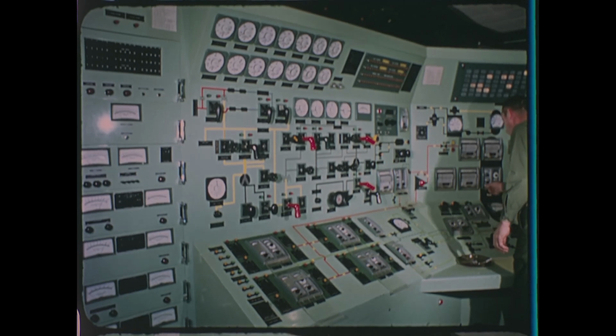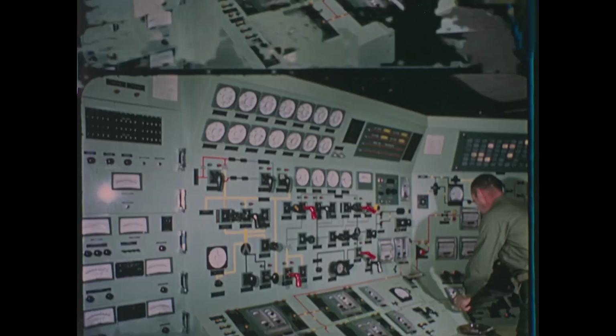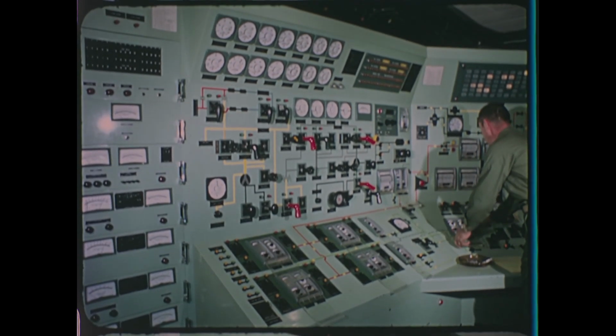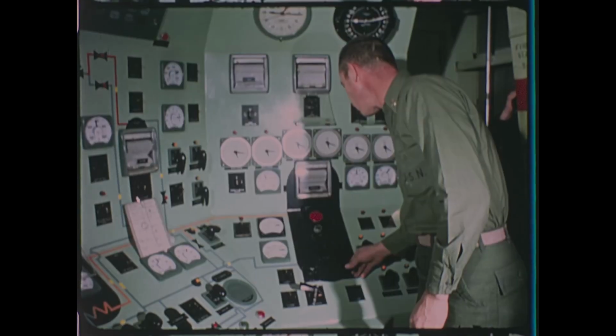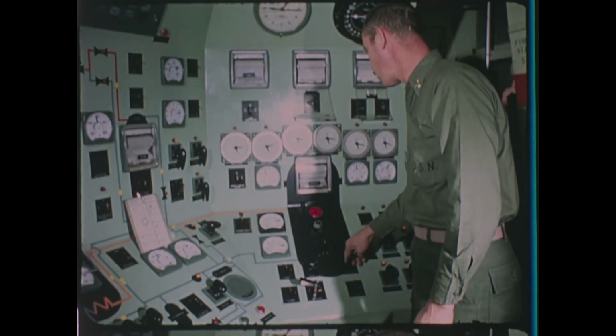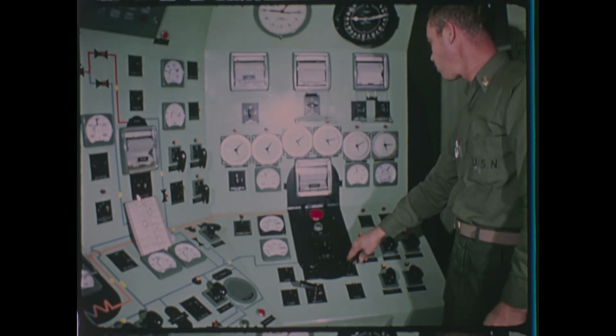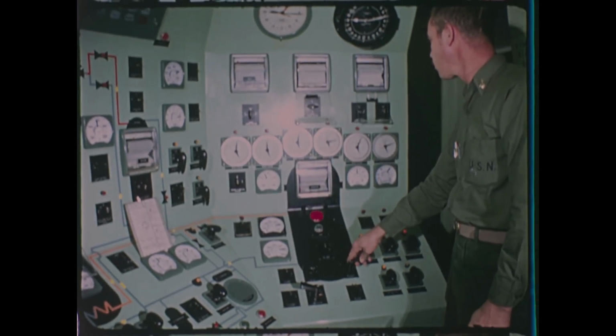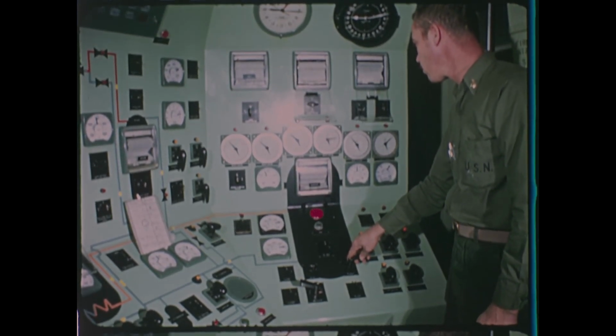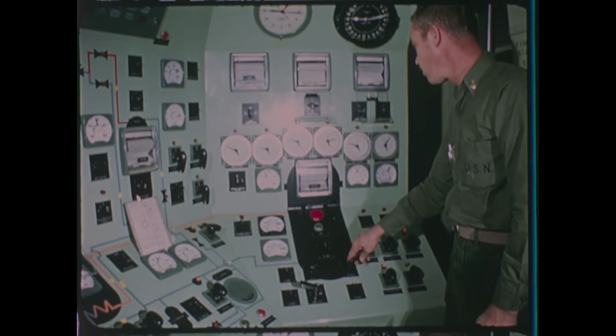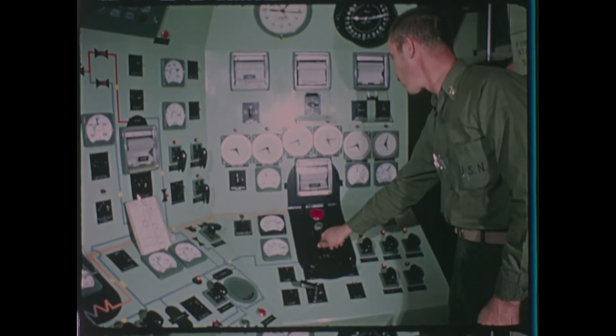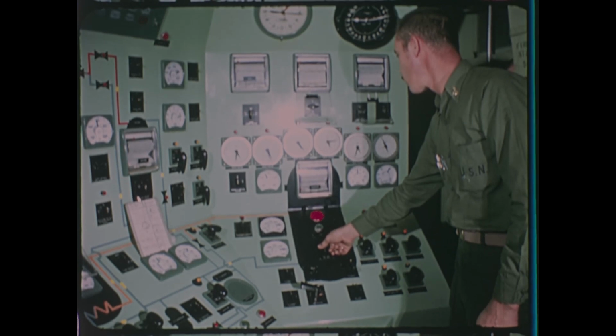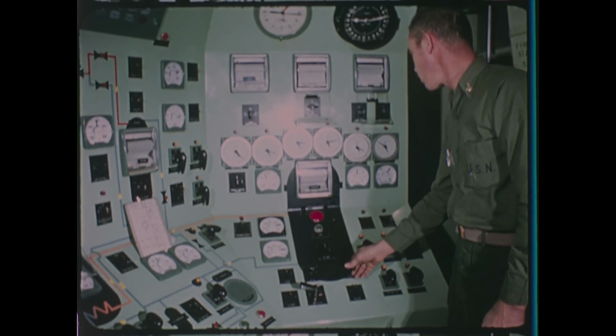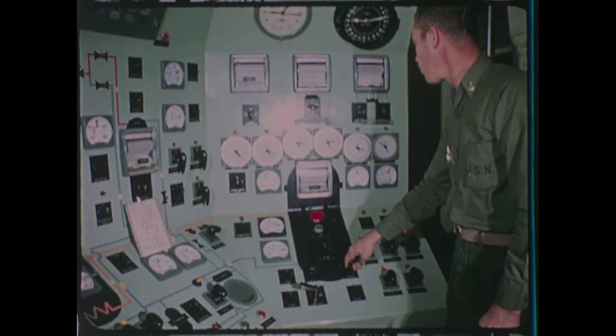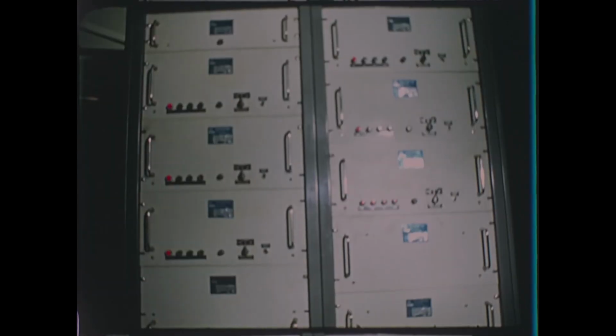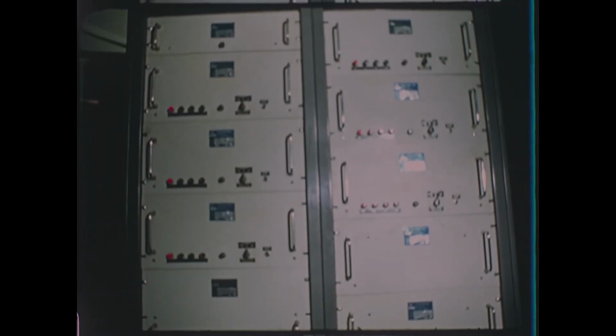To shut down the reactor with rod selector switch in the all position and speed selector in slow, operate rod motion control switch to the in position. Adjust individual rods to maintain rod position within 1/2 inch of each other. Should a low pressure annunciator alarm be received, place the low pressure scram bypass switch in bypass to continue with an orderly shutdown. Continue inserting rods until the position indicators are at 2 1/2 inches.